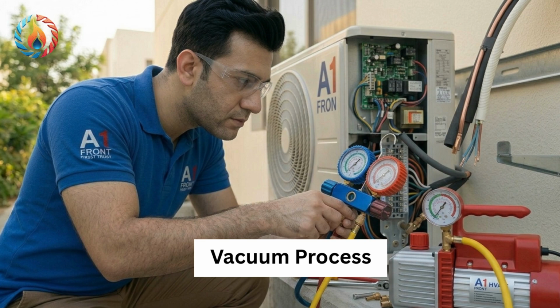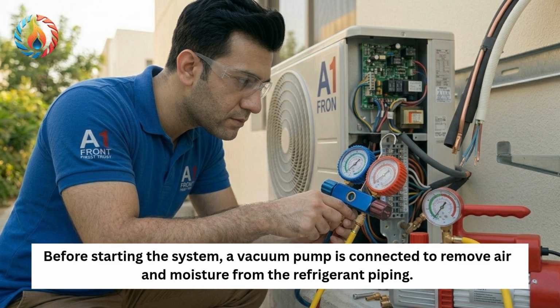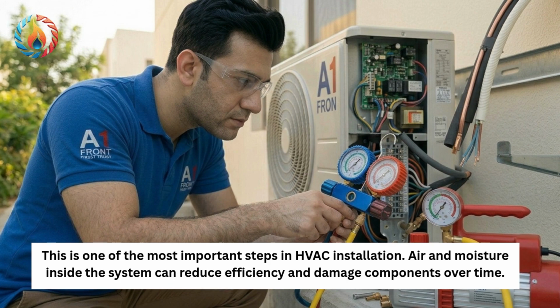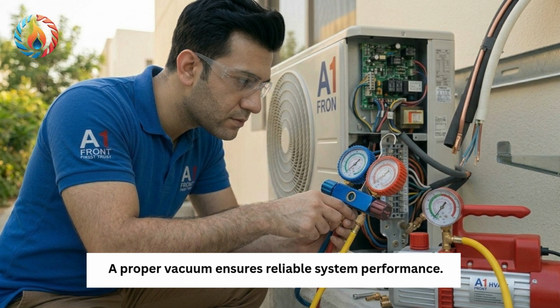Vacuum process. Before starting the system, a vacuum pump is connected to remove air and moisture from the refrigerant piping. This is one of the most important steps in HVAC installation. Air and moisture inside the system can reduce efficiency and damage components over time. A proper vacuum ensures reliable system performance.